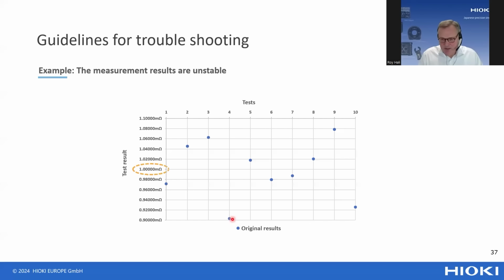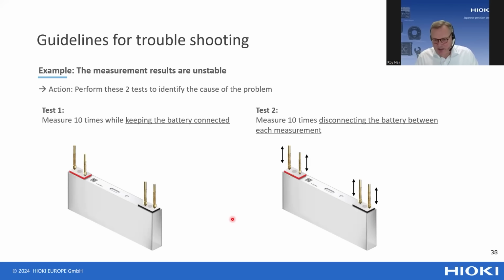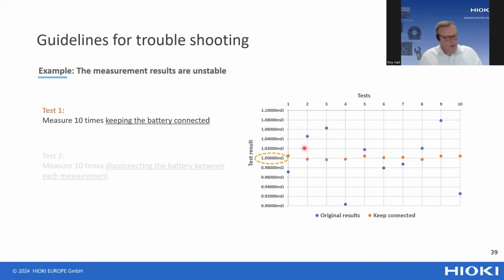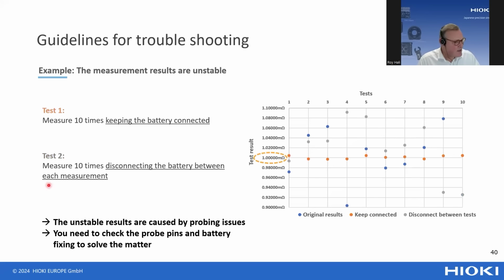What you can do in that kind of situation is to perform two different tests. To identify the cause of the problem, you're first going to do a test where you connect the battery and perform 10 measurements without disconnecting the battery. If in that case your measurement result is more repeatable, then you know that the cause of the problem is with the connecting to the battery. If you then perform a second test, where you disconnect the battery between each of the 10 measurements, and you see that once again there is a poor reproducibility of your measurement, then you absolutely are sure that making contact to your battery is the issue.